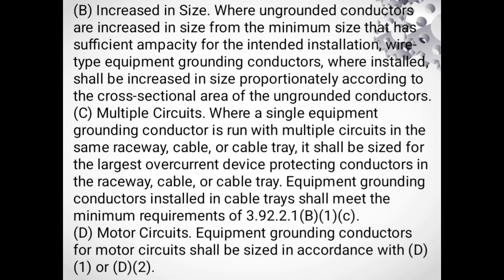B. Increase in size. Where ungrounded conductors are increased in size from the minimum size that has sufficient ampacity for the intended installation, wire type equipment grounding conductors, where installed, shall be increased in size proportionately according to the cross-sectional area of the ungrounded conductors. C. Multiple circuits. Where a single equipment grounding conductor is run with multiple circuits in the same raceway, cable or cable tray, it shall be sized for the largest overcurrent device protecting conductors in the raceway, cable or cable tray. Equipment grounding conductors installed in cable trays shall meet the minimum requirements of 3.92.2.1 B1C.